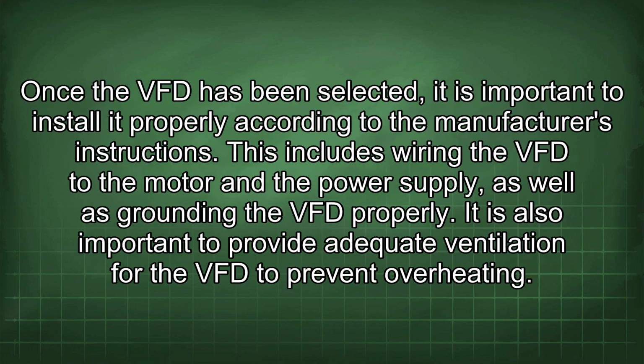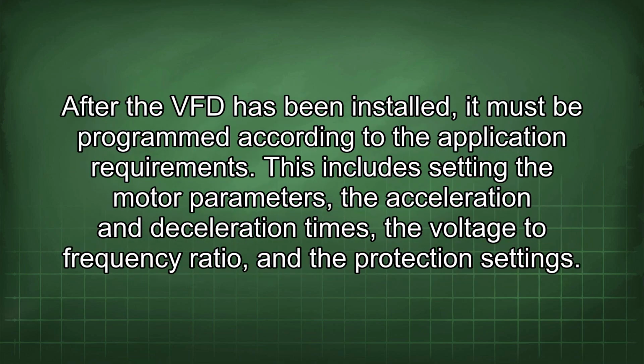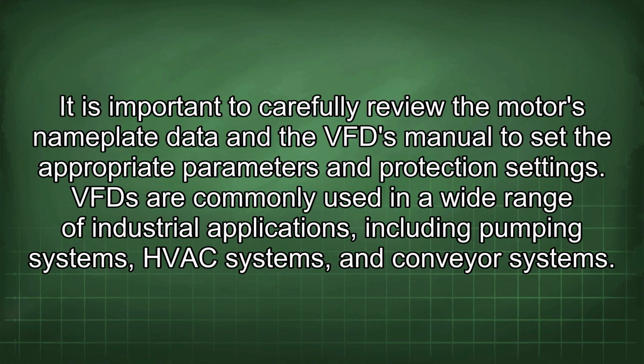Once the VFD has been selected, it is important to install it properly according to the manufacturer's instructions. This includes wiring the VFD to the motor and the power supply, as well as grounding the VFD properly. It is also important to provide adequate ventilation for the VFD to prevent overheating. After the VFD has been installed, it must be programmed according to the application requirements. This includes setting the motor parameters, the acceleration and deceleration times, the voltage to frequency ratio, and the protection settings. It is important to carefully review the motor's nameplate data and the VFD manual to set the appropriate parameters and protection settings. VFDs are commonly used in a wide range of industrial applications, including pumping systems, HVAC systems, and conveyor systems.